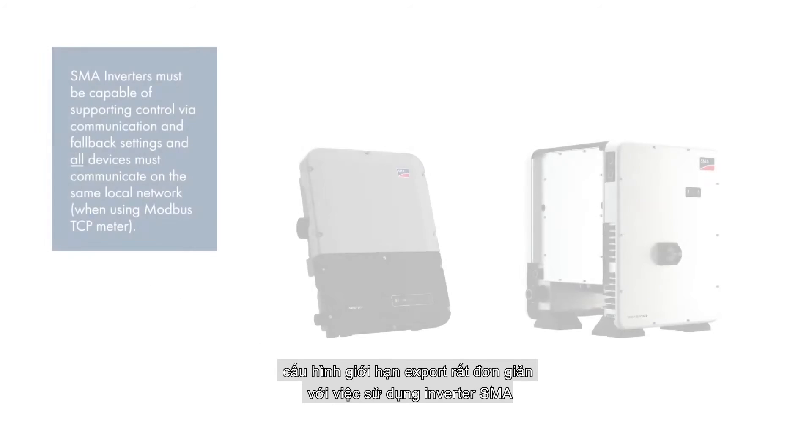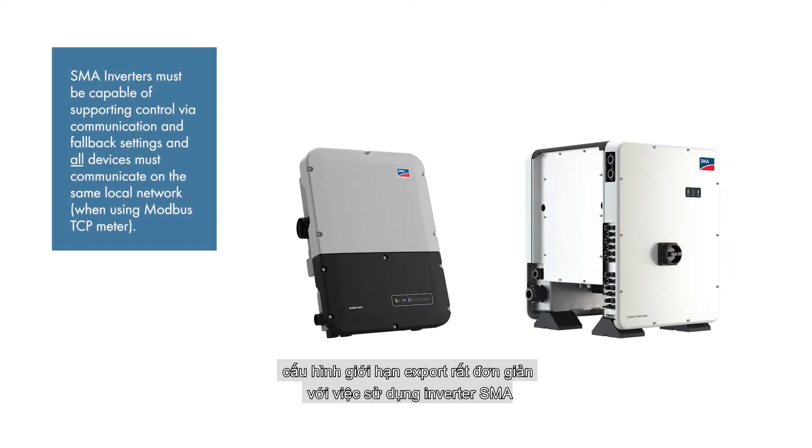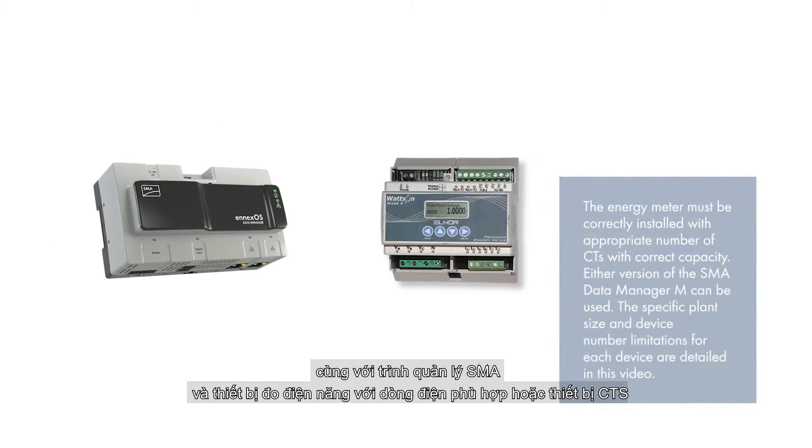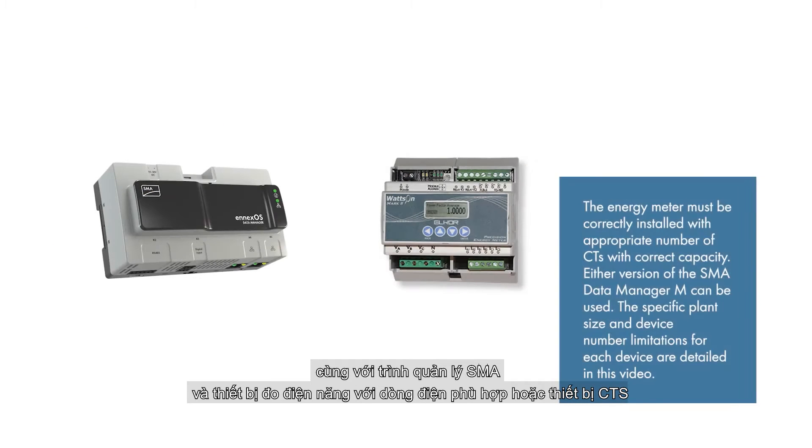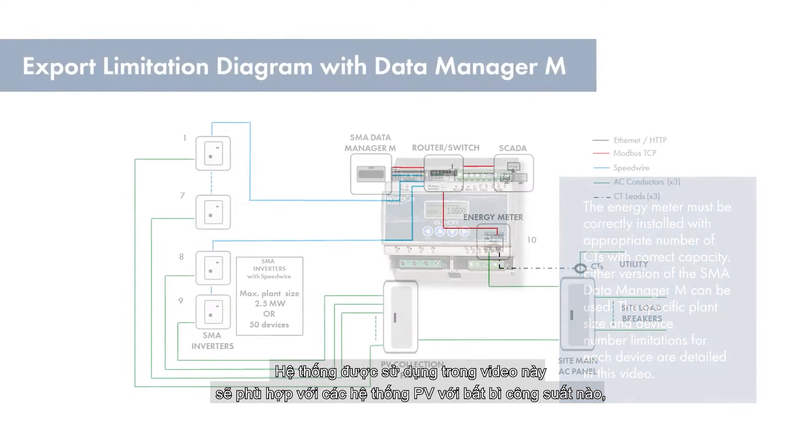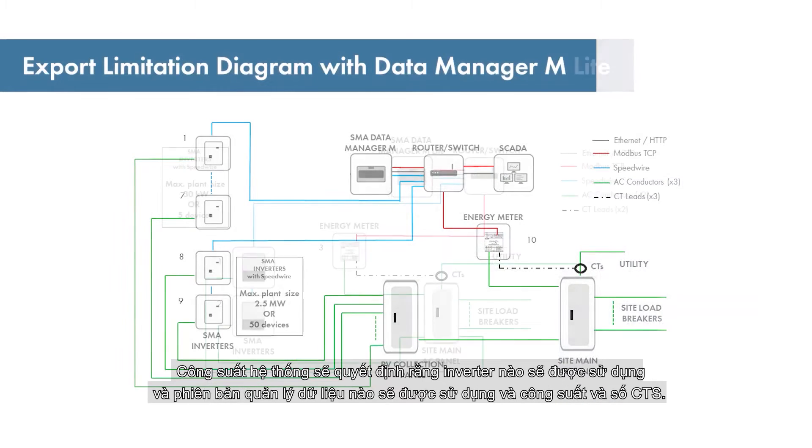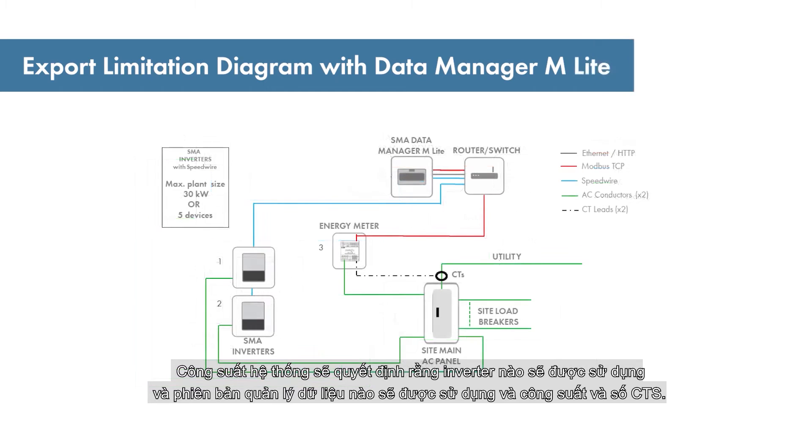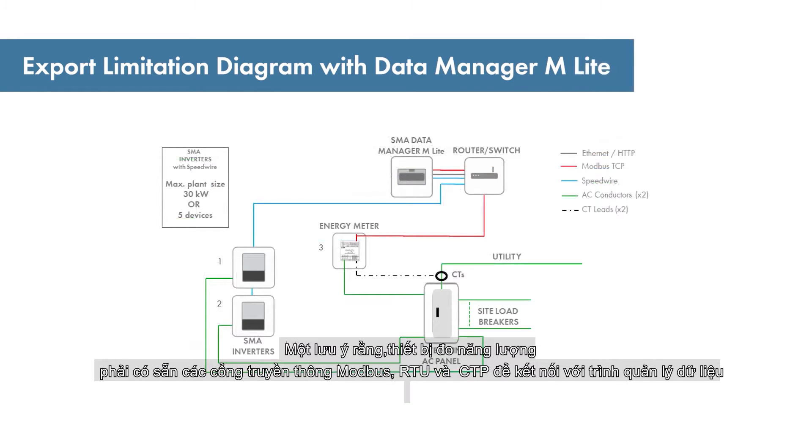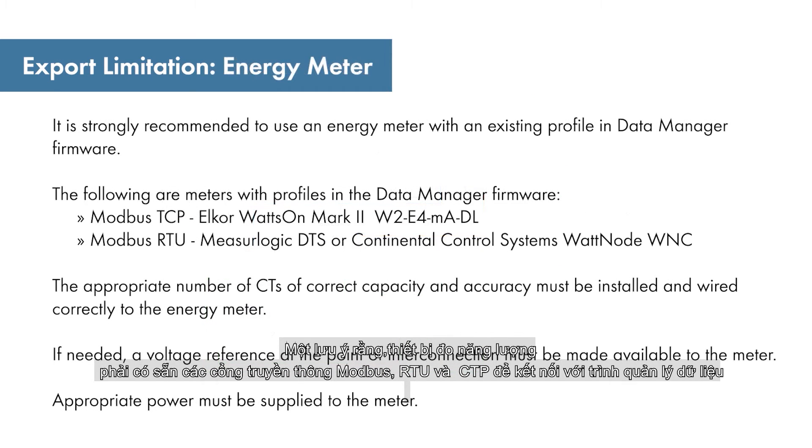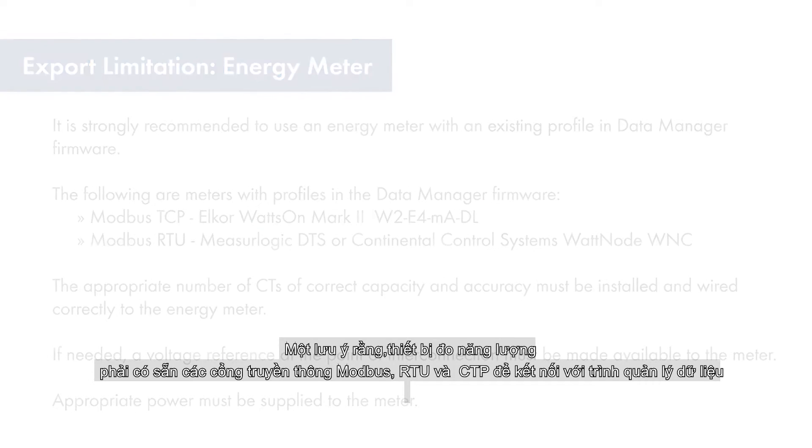Setting up export limitation is very straightforward using SMA inverters, an SMA data manager, and an approved energy meter with appropriate current transformers or CTs. The concept documented in this video is applicable to PV plants of any size. The size of the plant will determine which inverters are used, which version of the data manager is used, and the capacity and number of CTs needed. Note that approved energy meters are available for Modbus TCP and RTU communications to the data manager.